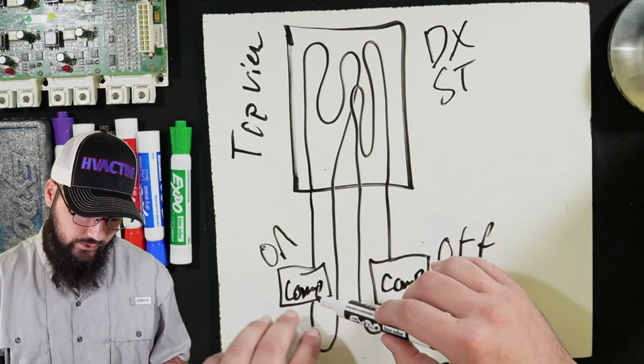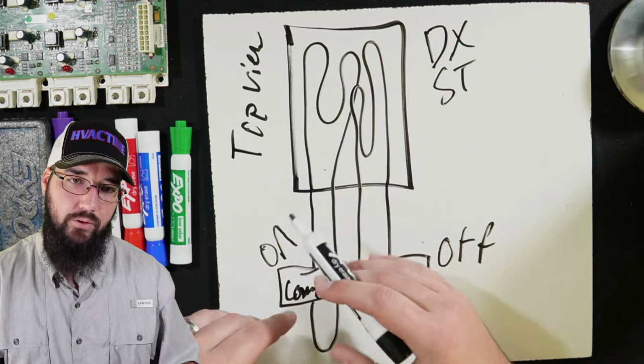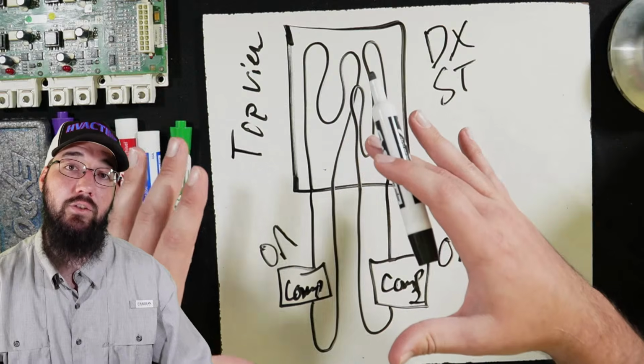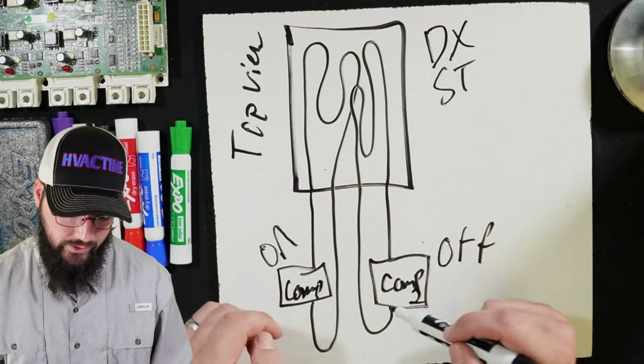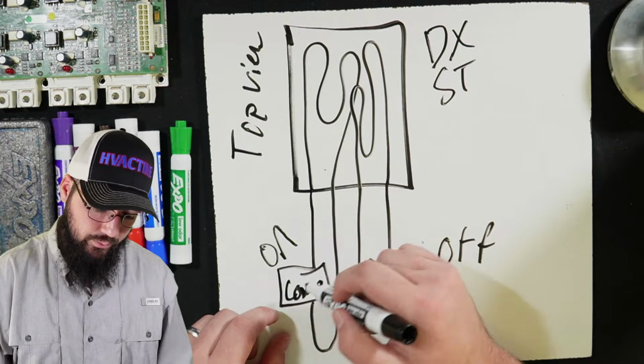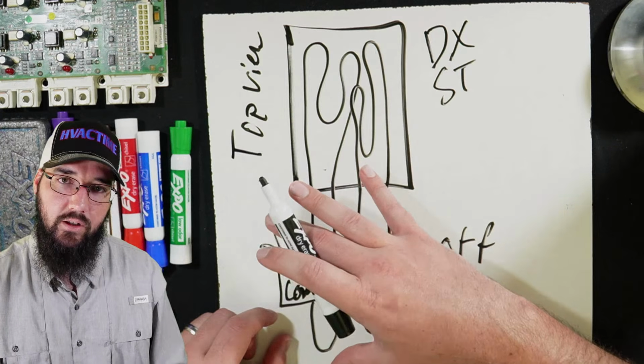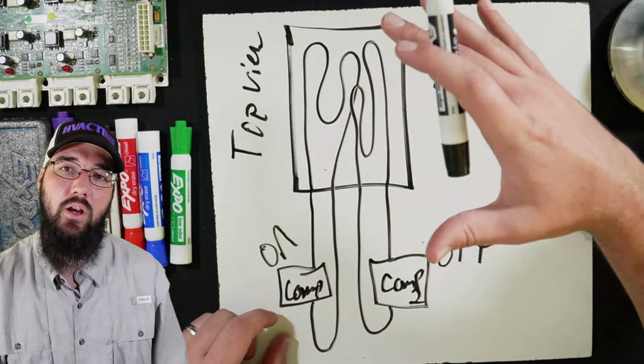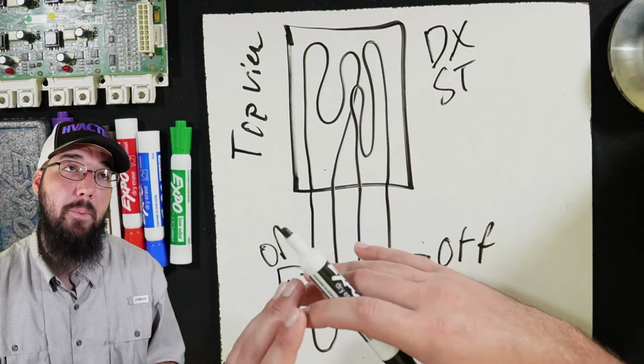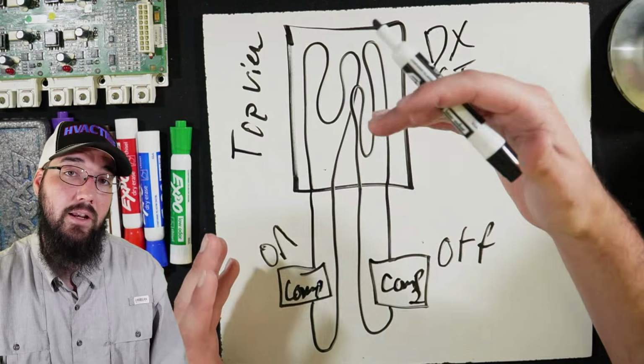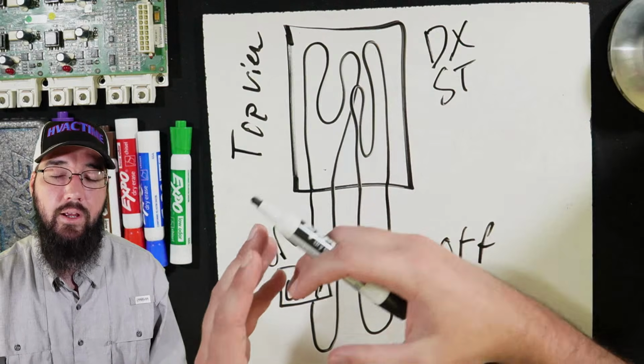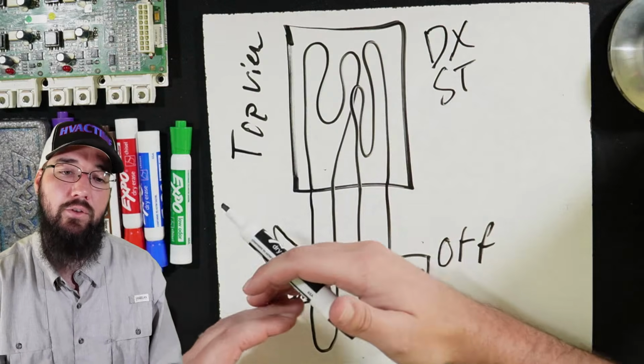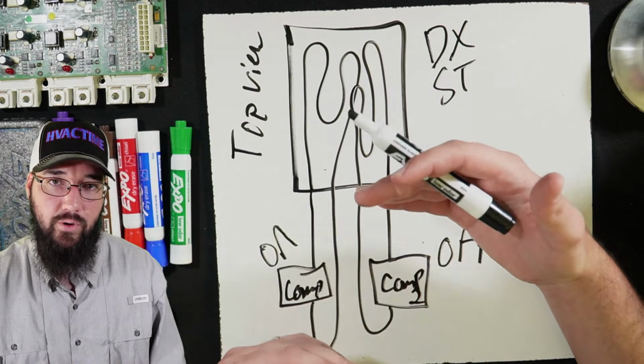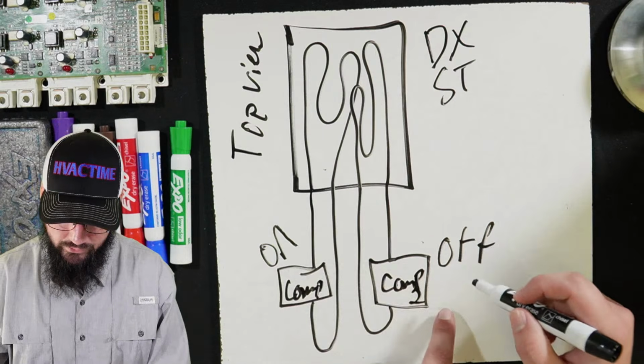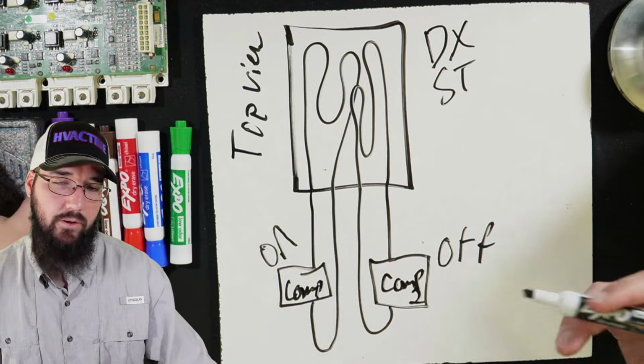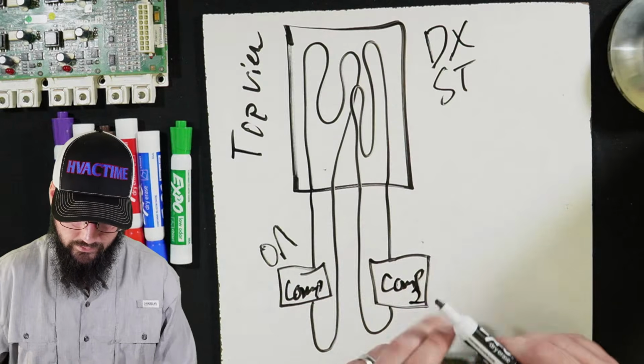What you'll see is this compressor will stage up. Let's say it stages up first to maximum on its own, and then the other compressor comes in to join it. This compressor will start off with a really low approach, and then as it runs up, the approach will increase, but depending on the circumstances, it may not hit maximum approach. We may not actually get to that full 10 degrees, even though the compressor is running at its max rate. It could, but it may not. And that's when compressor 2 gets called in, meaning these didn't turn on simultaneously.